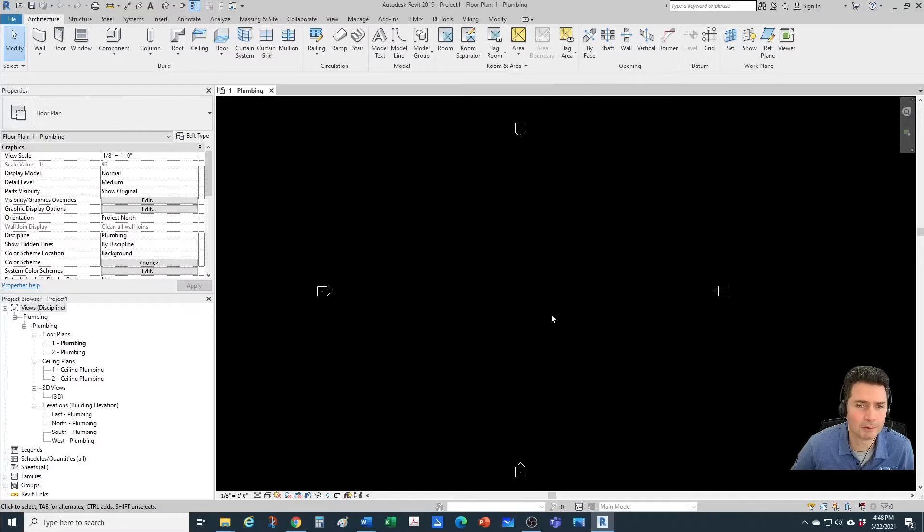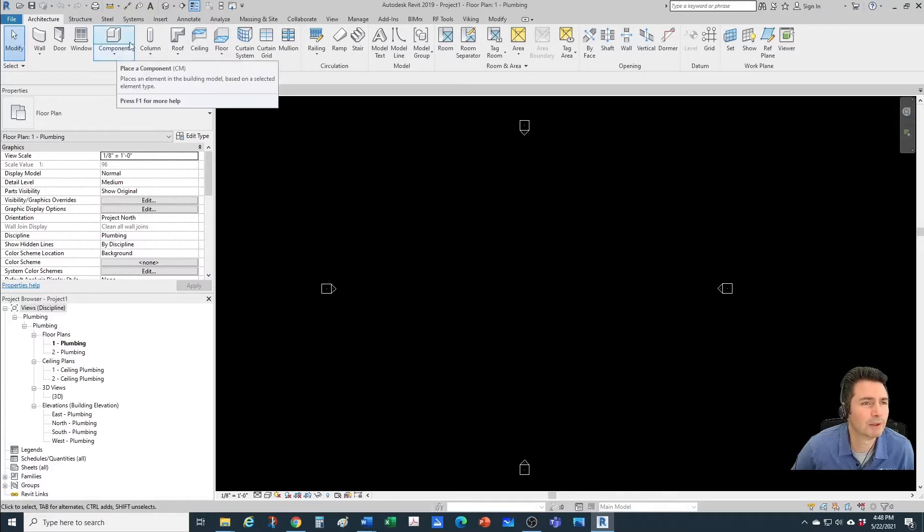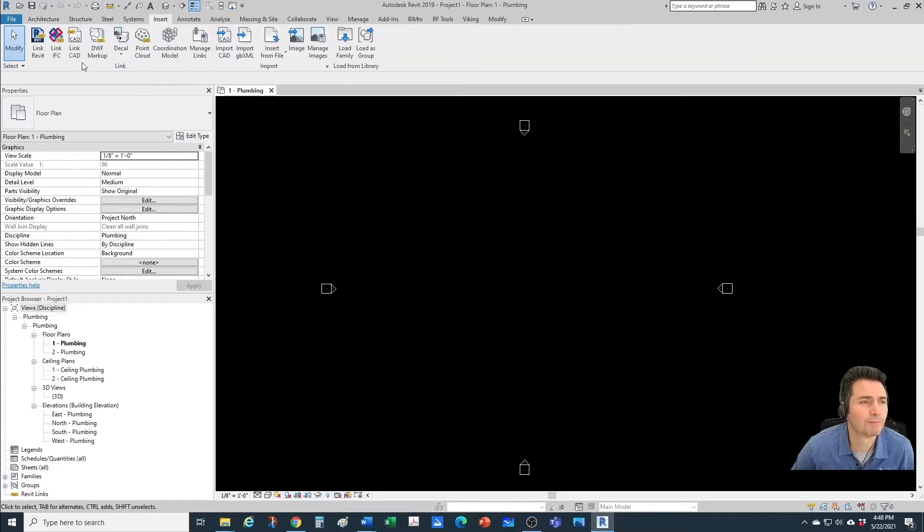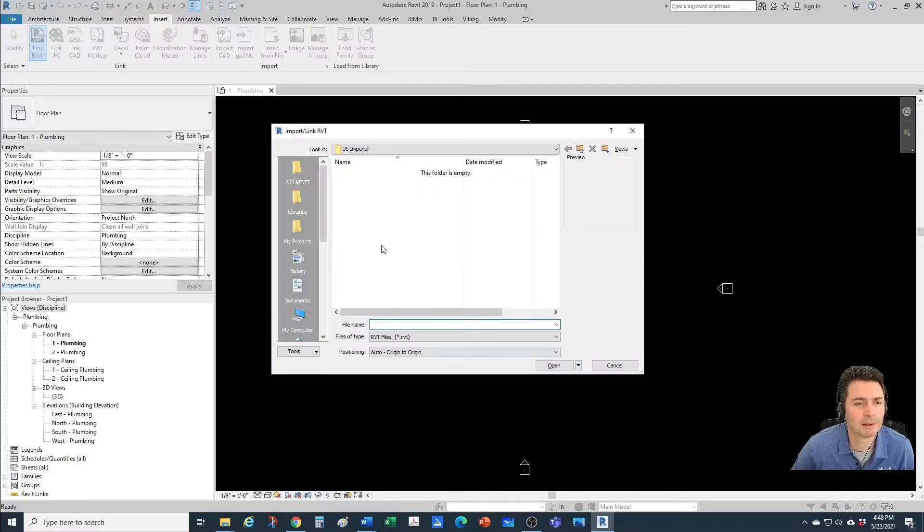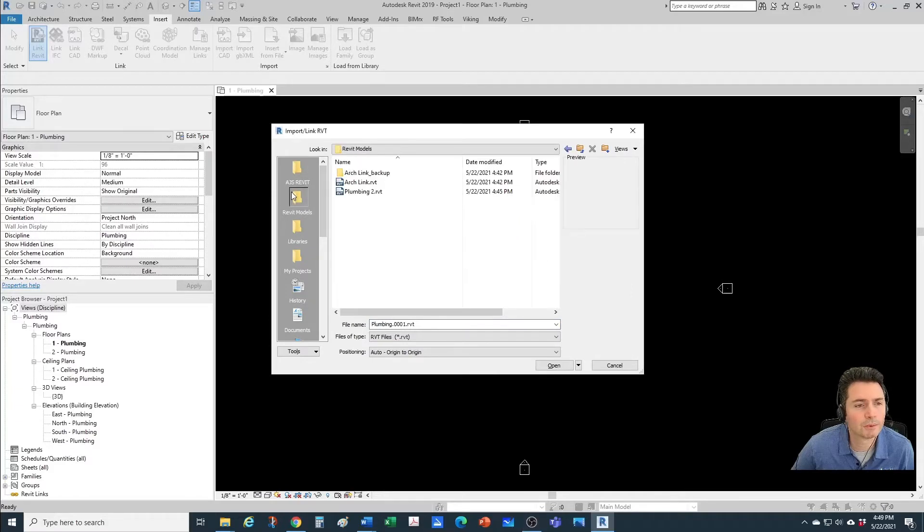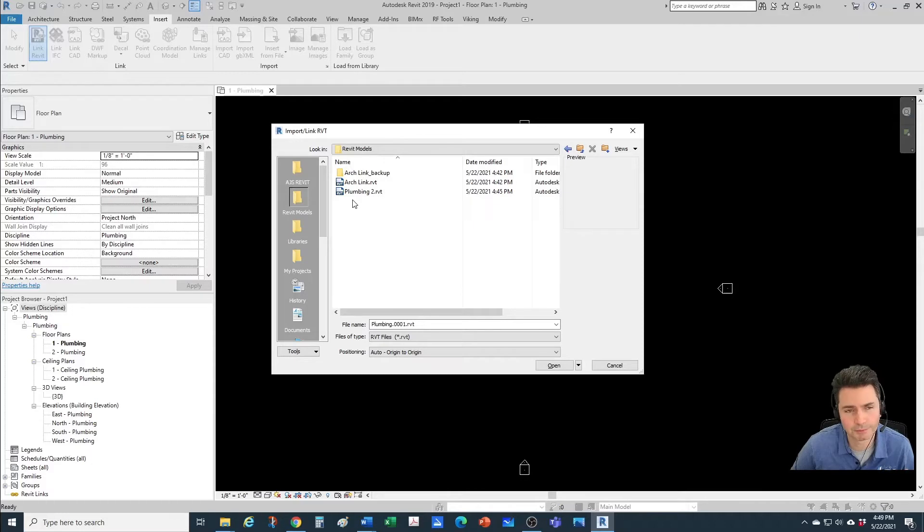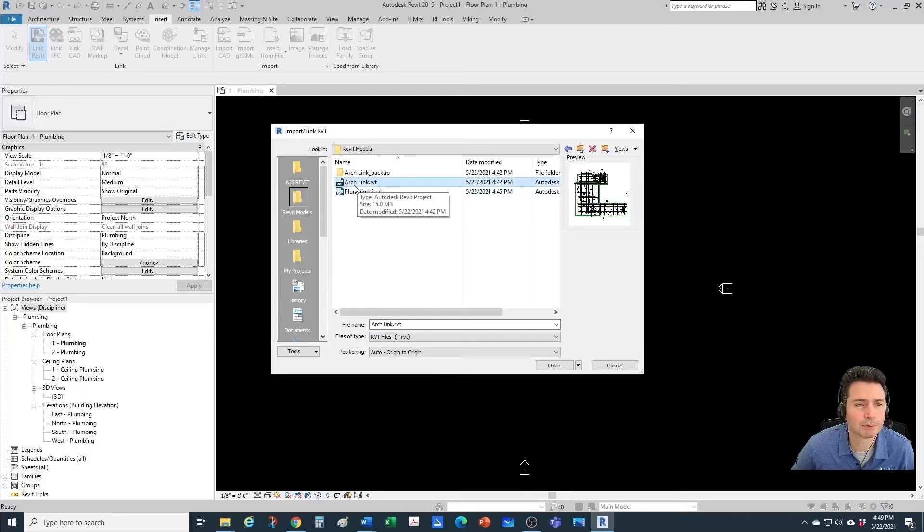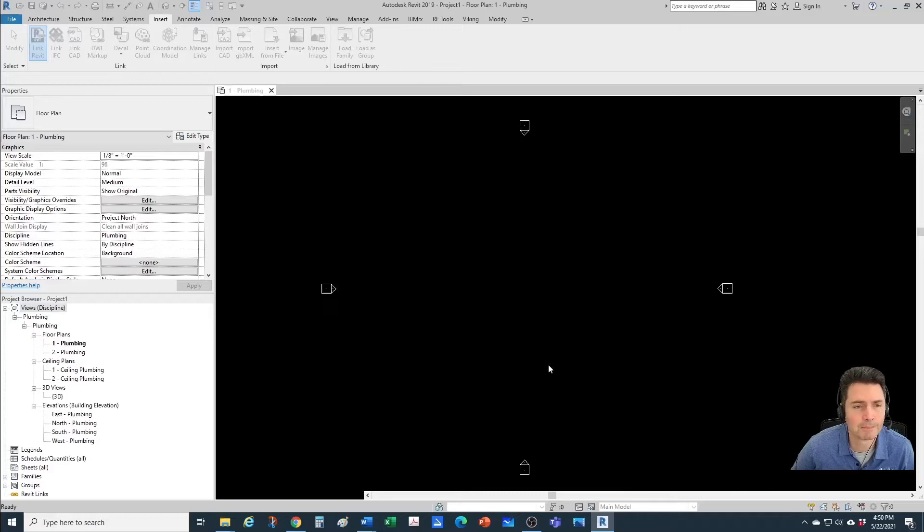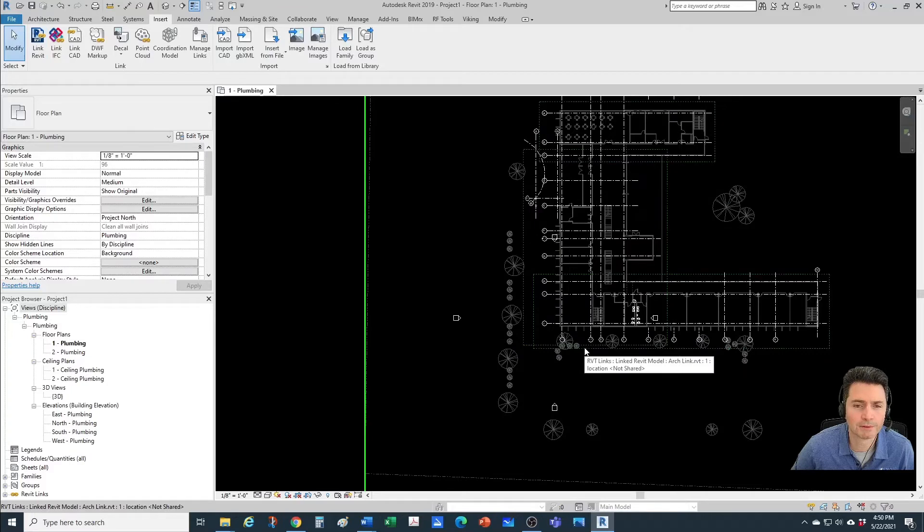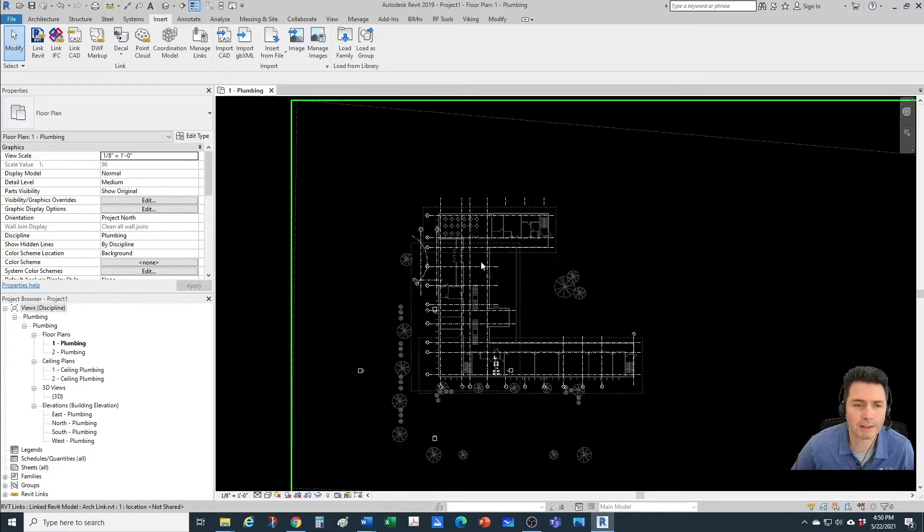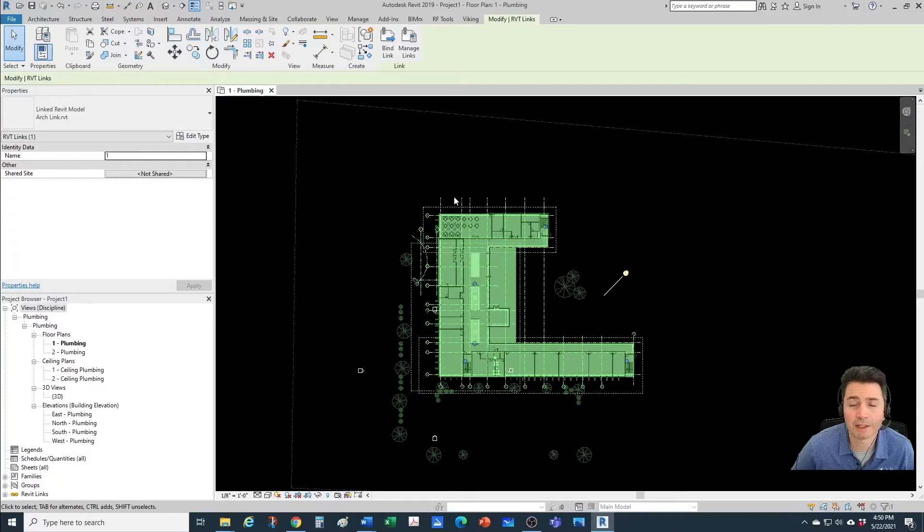Now the first step would be to link in our architectural model. In order to do that, you would come here to Insert, then Link Revit, and then we would browse to that location. You browse to whichever location you have your architectural links located at. In our case, we're going to use this Arch Link Model. We're going to use this position as Auto, Origin to Origin. That's the most common one. And here it is. Now it's always a good practice to click on your model and pin it down so you don't move it accidentally.